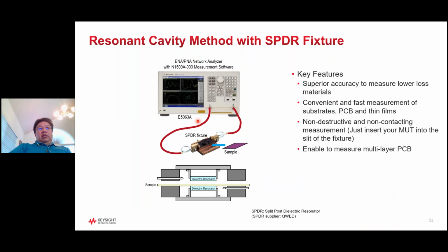So how does it work? First, let's look at the SPDR. Basically, it's simple. Inside there are two cables or loops that do signal coupling, and you slide your sample in. The idea is you want your sample to lie flat against the bottom half. If your sample is away from the bottom, let's say towards the center, it affects your measurement accuracy.